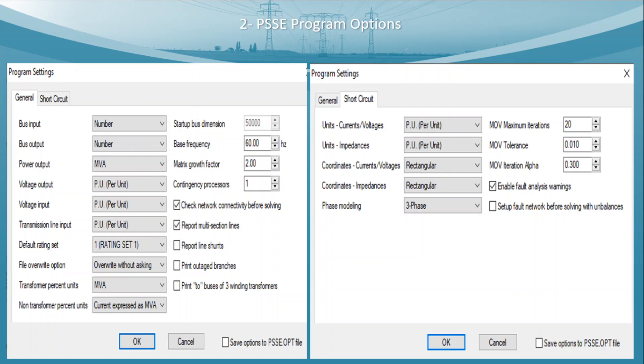In PSSE Program Options, bus inputs and bus outputs are taken as numbers. All these settings should be done before starting your case. The most important factor is the base frequency, which differs for different countries — so first check your frequency settings, whether your frequency is 50 Hz or 60 Hz. In the case of short circuit analysis, you can select per unit or physical results, and rectangular or polar phasor currents, all from the Program Settings option.